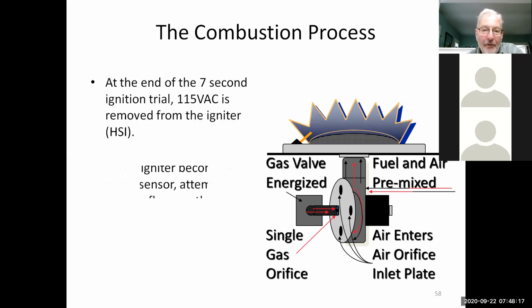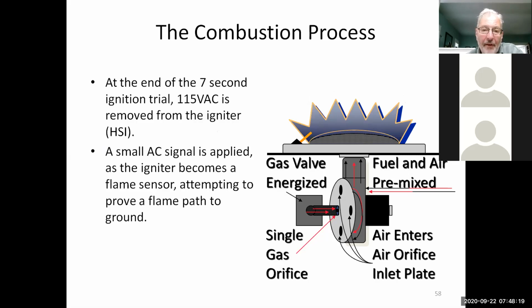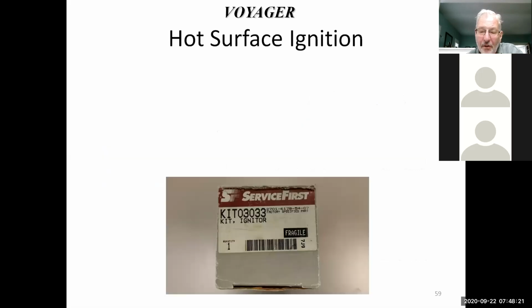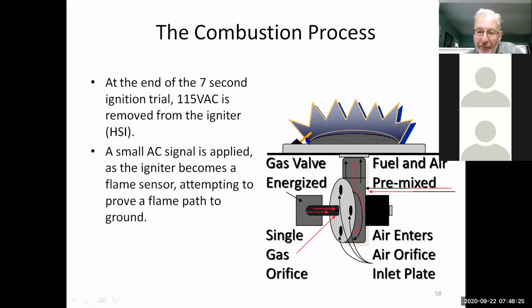The combustion process, again, at the end of the 7-second trial for ignition, the igniter becomes the flame sensor. So this igniter has 110 volts to it while it's trying to light. Once it lights, it runs at about 50 to 60 volts, and it senses the flame in the unit, okay? And that's how we sense flame on these.